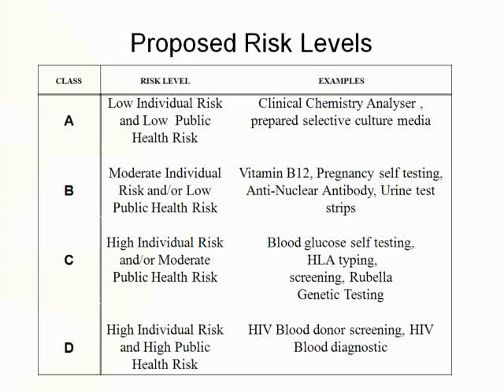And then levels B, C, and D would all have some oversight by a notified body, with increasing oversight as the risk level increases. And Class D would pretty much reflect the current List A requirements, although there may be additional products put in based on risk. It would then be up to the individual manufacturer and their notified body to determine which risk level a particular in vitro diagnostic is classified as.